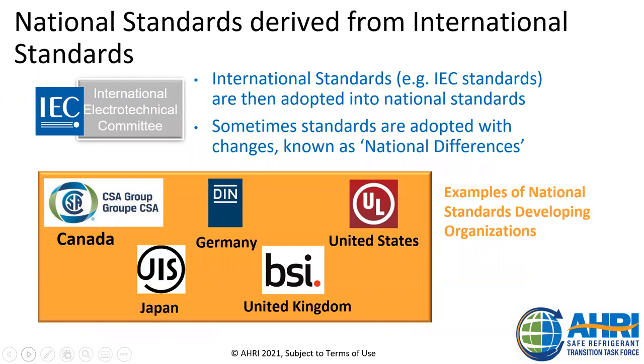So some national standards are actually derived from these international standards according to the agreement. This phenomenon is very much prevalent in the HVAC industry. It is also used in the auto industry and a lot of other industries and, in fact, other countries. In fact, all world regions that use Class A2L refrigerants certify to safety standards for air conditioning and heat pump systems that are a derivative of the IEC standard. Now, for the US too, the safety standard for air conditioning and heat pumps was first written by the IEC. It's called the IEC 60335-2-40. And then it was adopted as a national standard with deviations under the ANSI accredited process by an SDO called UL Standards. The standard is called UL 60335-2-40. The number remains the same, the SDO changes, right?